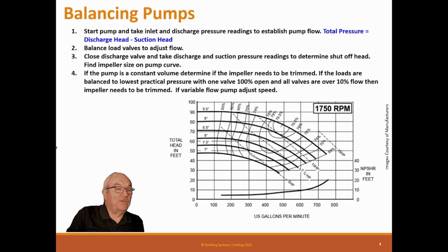And so they do. So it's all kinds of different inches. Now, what you want to know is if you need 400 GPM at, say, right here, which would be, if they've done it correctly, they should have provided you a 7.9-inch impeller, maybe, because right here's an 8-inch impeller curve. And so how you find that is you get your GPM, you get your head, and you go across the head until you hit that curve. If you got an 8-inch, then right here would be the flow that pump is capable of at that head.